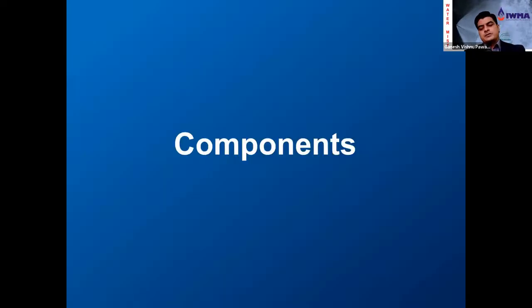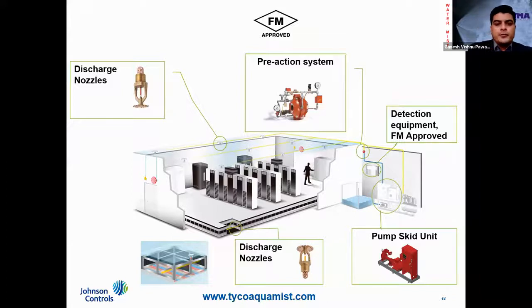Now, what are the key components of this system? For the protection of the above floor area, we use pendant type water mist sprinklers, whereas for the raised floors, we use sprinklers with upright orientation. A single interlock pre-action system was used with a discharge delay of 30 seconds. Then the FM approved pump skid, and of course the detection system. It is very essential to know that all these components have to be FM approved. So all the components listed here, valves, the water mist pump skid, or the nozzles, have to have FM approval.